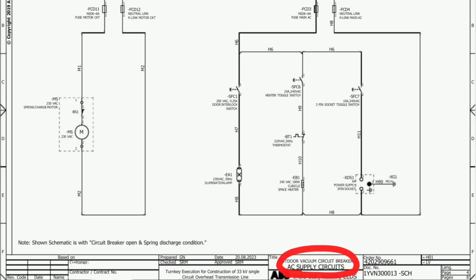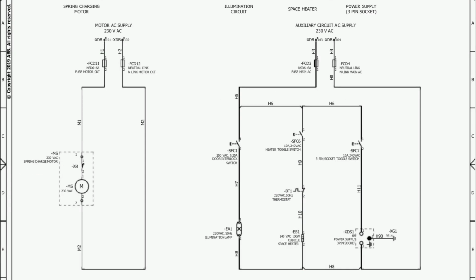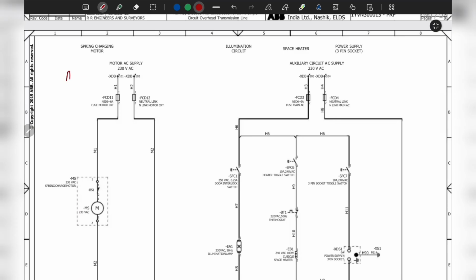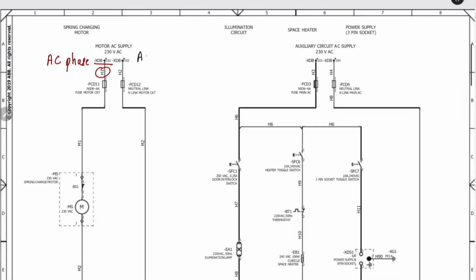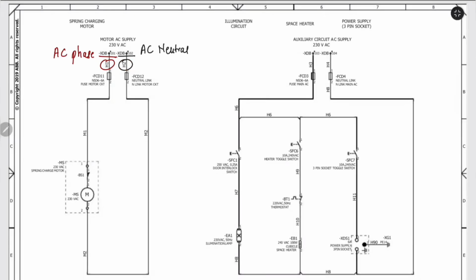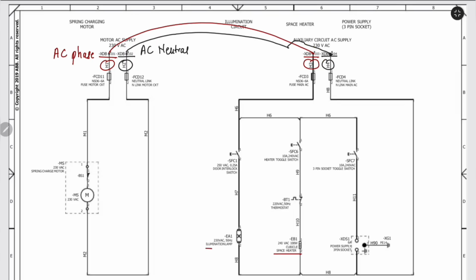AC supply wiring. Our first step is energizing the breaker's internal auxiliary circuits. The AC supply powers the spring charging motor, space heaters, cubicle lamp, and service socket. Connect the AC phase to terminal XDB101, H1. Connect the neutral to terminal XDB102, H2. Now install jumpers from XDB101 to XDB103, H3, and from XDB102 to XDB104, H4. These jumpers distribute power to the internal heater, lamp, and service socket.